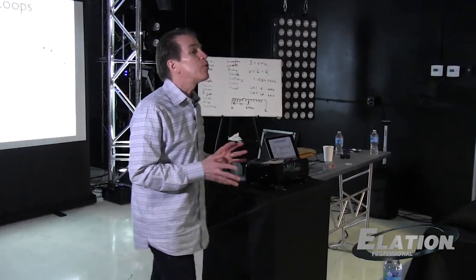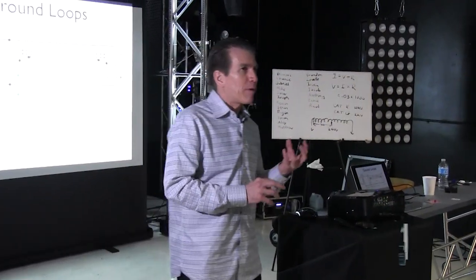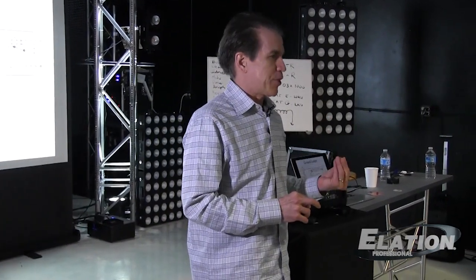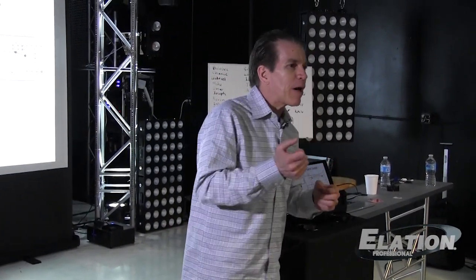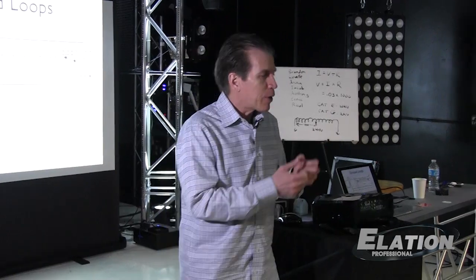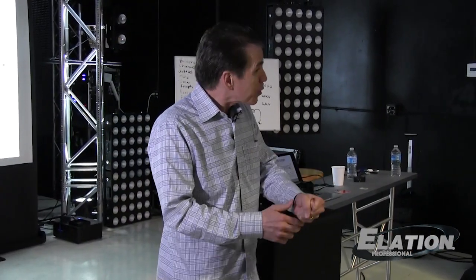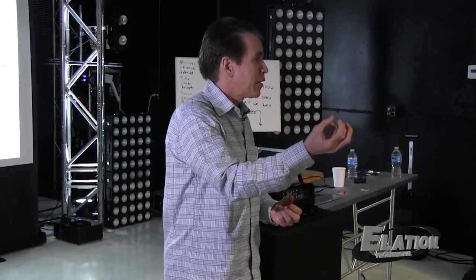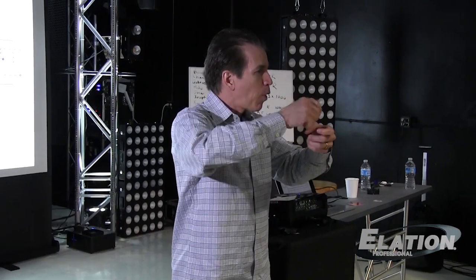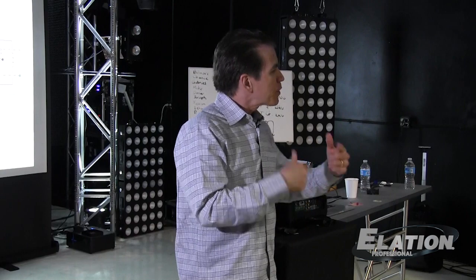Part of that has to do with the effectiveness of the connection, because when you take a grounding electrode and connect it to the earth and then to the electrical system, it has a connector on it. Typically the connector has bolts or nuts that you tighten down and it clamps onto something. Over time the connection degrades and you don't have a good connection to earth.